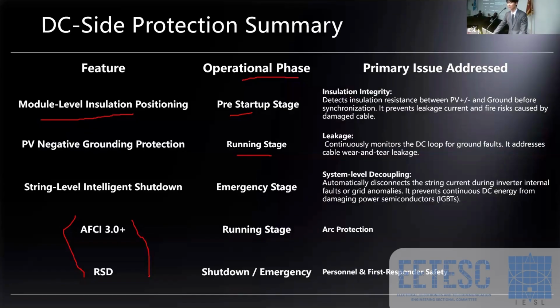It has 10 MPPT separately, and we are equipped with 2 separate intelligent switches, and every 5 MPPT will be connected to one switch. If somewhere some string level MPPT is wrong or something emergency happened, the other 5 strings will work normally. So that's the string level intelligent shutdown.